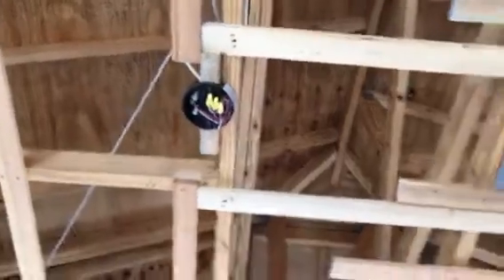We come back out of the switch box. In this case we're running a rope light into a soffit right here. These rooms have to be on arc fault circuits, so what we try to do is run everything in a loop. We came down, ran one wire around, put them through sleeves in studs, and ran over to this outlet here.